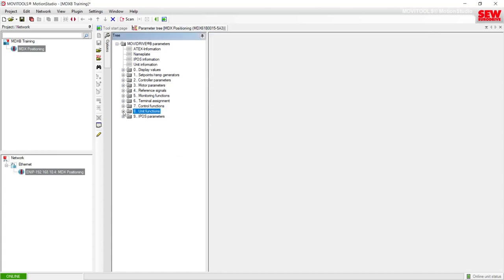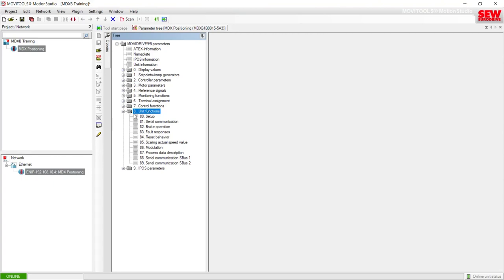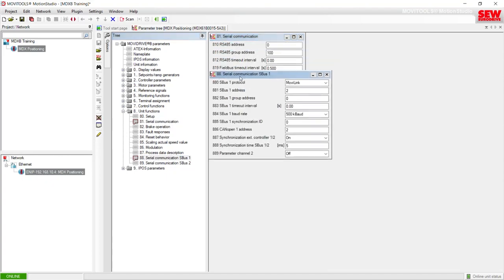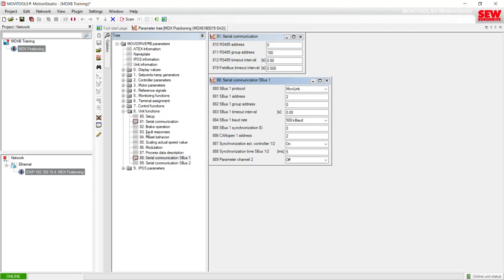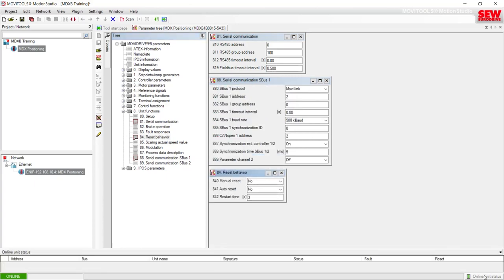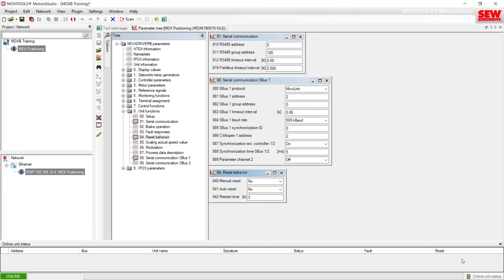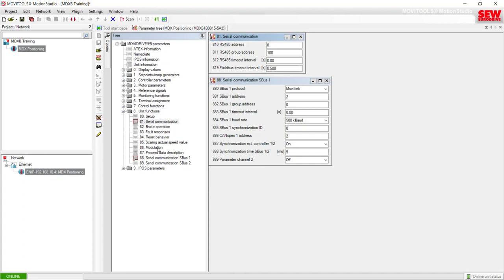For folder group 8, Unit Functions, this is where you can delivery-state the MOVIDRIVE, set the address for serial communication and SBUS communications. You can also do a fault reset manually through parameter 840 — this is an alternative to using the online unit status window to reset a fault; you can just come to parameter 840 and toggle a manual reset. In the next lab, we will change the modulation frequency during startup so that the MOVIDRIVE runs quieter.